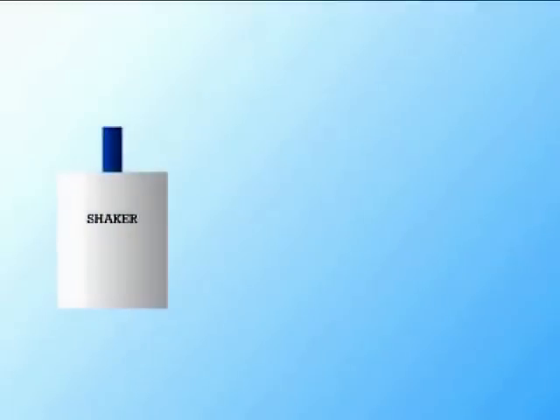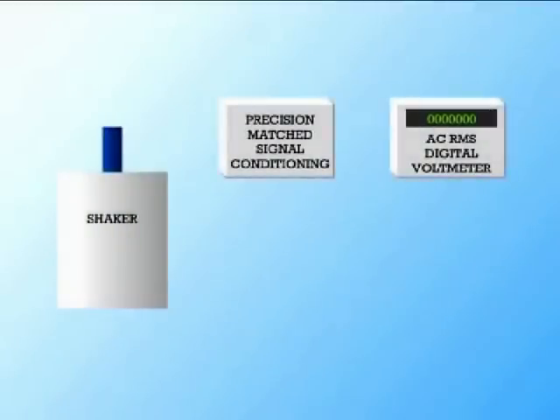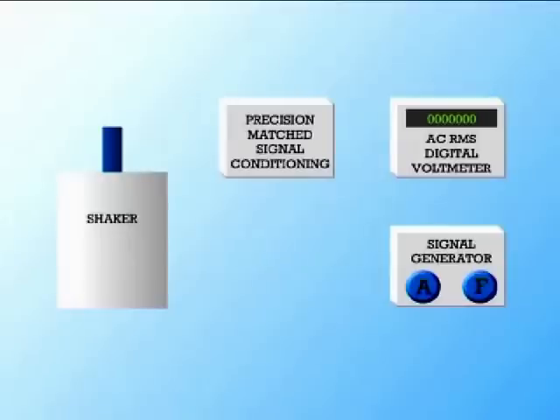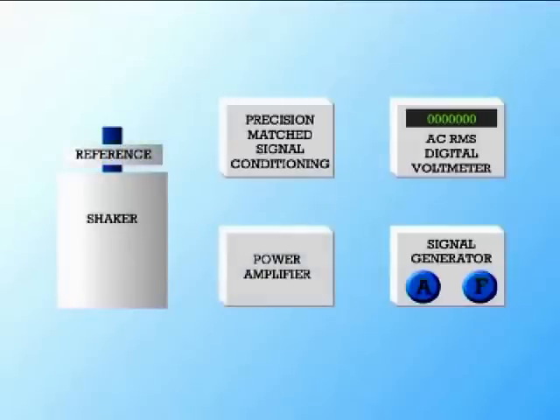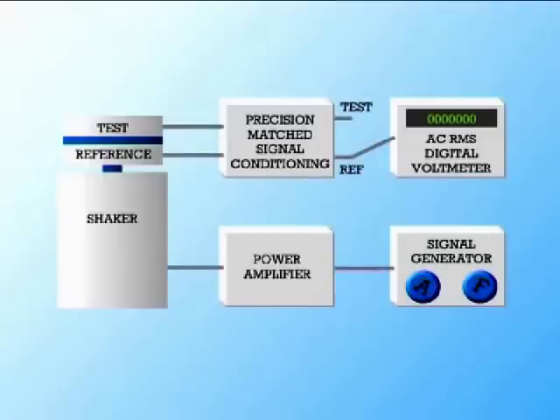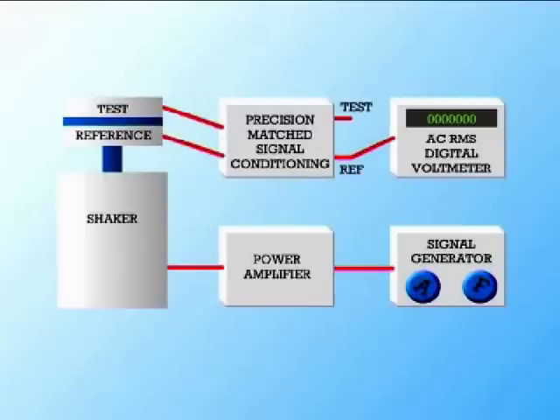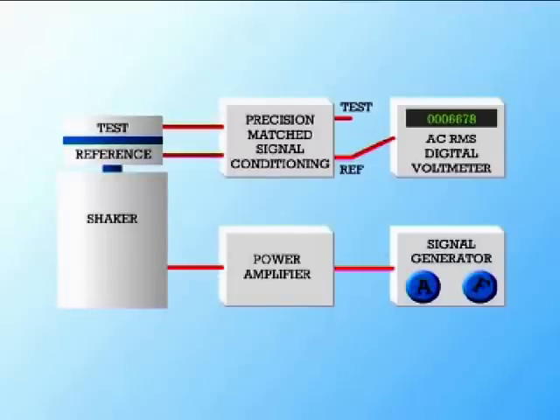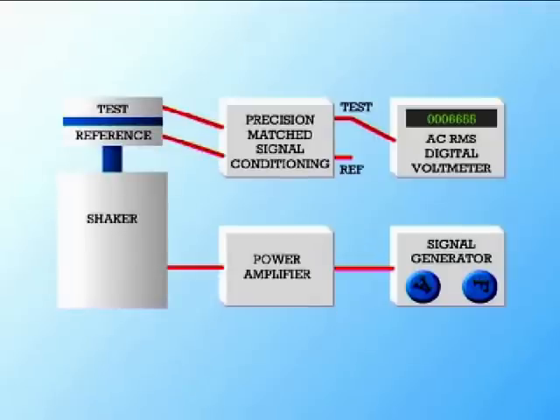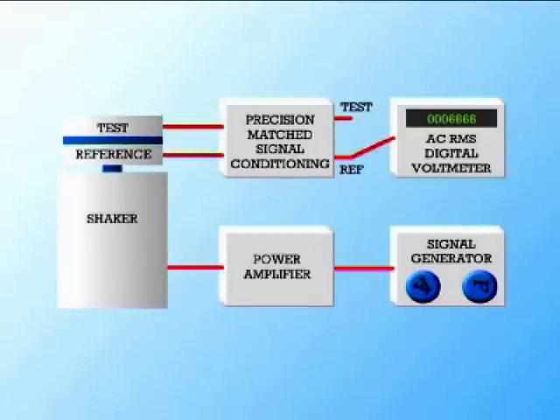Traditional manual calibration methods are time-consuming and require a number of separate components to be assembled. The process involves mechanically mounting the test sensor on top of a known reference sensor and manually setting a number of known frequencies and amplitudes on the signal generator. With the switch set to ref, the amplitude level is manually tuned at each frequency, and once stable, the switch is set to test and the unknown device measured. This is repeated until the complete frequency range is covered, with the full calibration typically taking 30 to 40 minutes, including manually documenting the results.